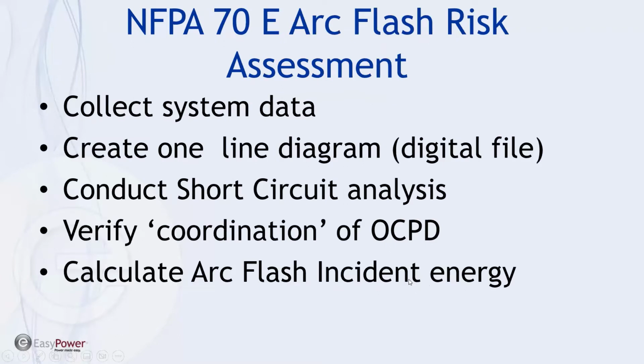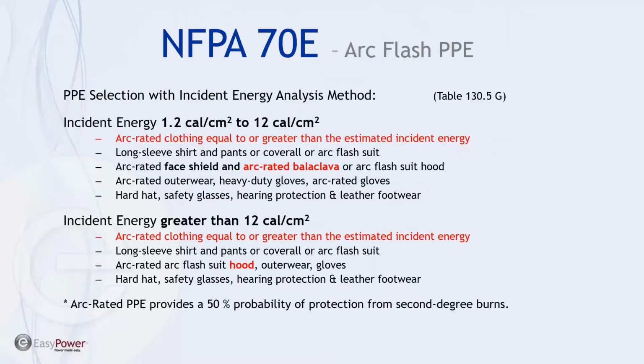So an arc flash risk assessment basically consists of collecting the system data, creating a one-line diagram, which is a digital file that incorporates this data, then conducting a short circuit analysis to determine the maximum current at any particular location in the system, and then calculating incident energy as a result of how the overcurrent protection devices react to that level of current. NFPA 70E describes two categories of PPE once you've used incident energy, and this requires that the PPE selected must be equal to or greater than the incident energy calculated. The two categories are 1.2 calories to 12 calories, and then greater than 12 calories, the primary difference being that below 12 calories, you can use an arc-rated balaclava. Above 12 calories, it's required to use an arc flash hood.